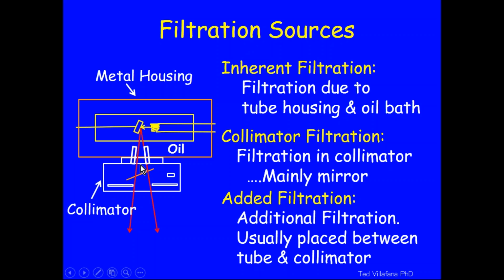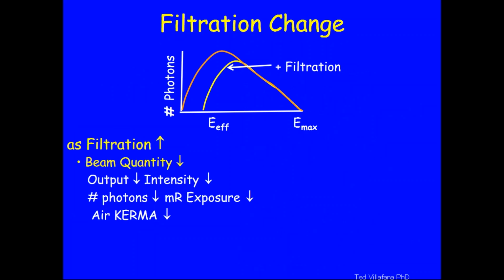But as I said, in the U.S., we typically don't use added filtration in radiography. In Europe, the technologists like to use filters, and they vary the filter depending on the needs of the patient. Typically, we don't do that in the USA. We work with fixed filtration, typically in radiography. But let's see what happens when you add a filter. Take a look at the curves of comparison. The red one is before you put in the filter, let's say, and the yellow one is after the filter. Let's make some very important observations.